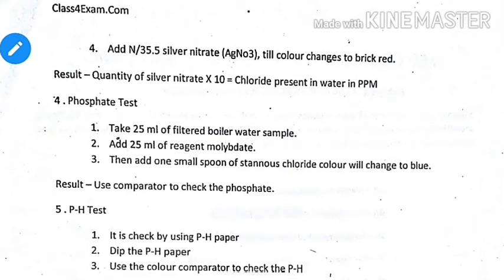Phosphate is added to boiler water to remove scale. Scale is formed by calcium carbonate, calcium sulphate, calcium chloride, magnesium sulphate — any sulphate, chloride, or carbonate compound can form scales in the boiler water. This scale formation is a major cause of overheating, as it reduces heat transfer, can lead to tube failure, and increases costs. Phosphates and anti-scalants are used to prevent scale formation. If the phosphate level is low, scale formation increases and the hardness of the boiler water will also increase.